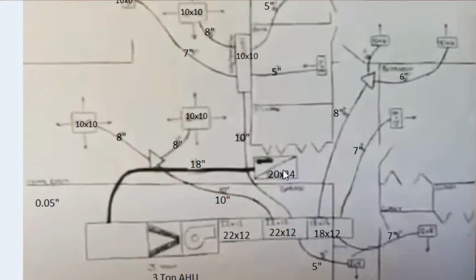So we add all this up. We add the length of this flex minus any loss in the actual fitting here on the return. We do the same for our supply. We add all of the straight lengths up, and any losses in fittings. So if we've got a 90, we've got to add so many equivalent feet for that. I have another video on how to determine that.